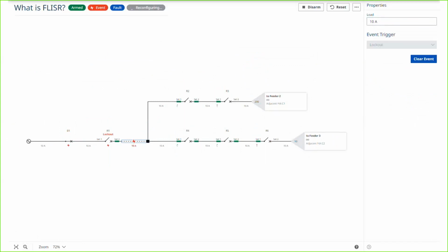So same situation here, recloser 1 locks out. FLISR will isolate the fault, and it will sectionalize the outage territory. So the area between R4 and R6 is too big for feeder 3. So we open R5, and we leave the area between R4 and R5 de-energized due to a capacity limit. We're unable to pick up everything because feeder 3 is heavily loaded.